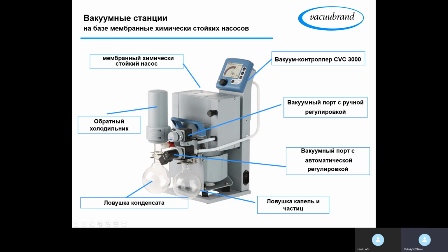Here we have quite a special vacuum pump that I personally never sold, and I'm not quite sure if there are many around. But this is a pump that can control 2 different applications simultaneously, which is pretty unusual. The advantage of this kind of pump is that, first of all, it can save space, it can save some energy, and it can save some money, because to buy 2 separate pumps is definitely more expensive than to buy one pump with 2 controllers.